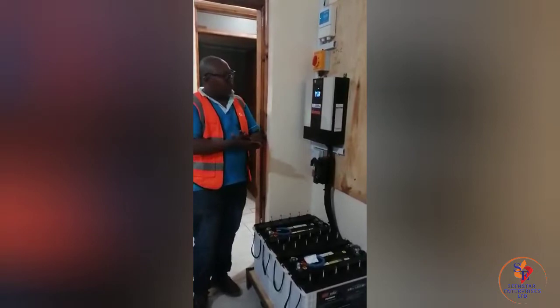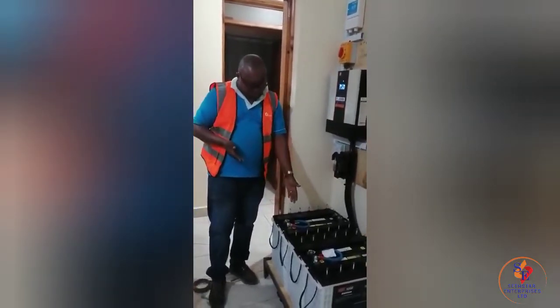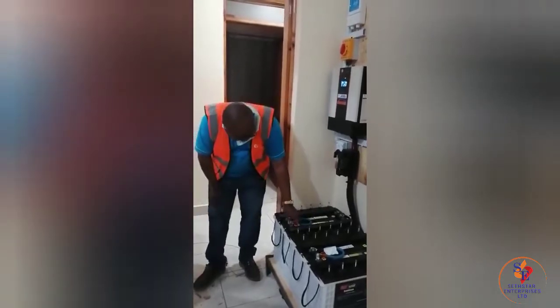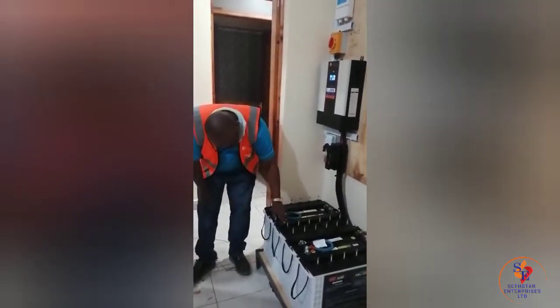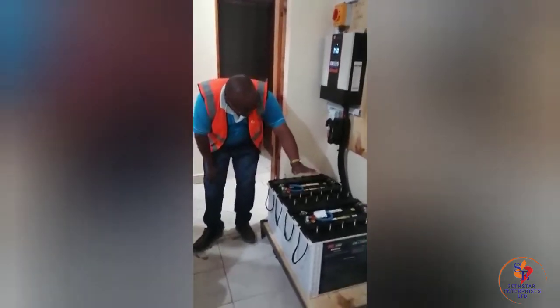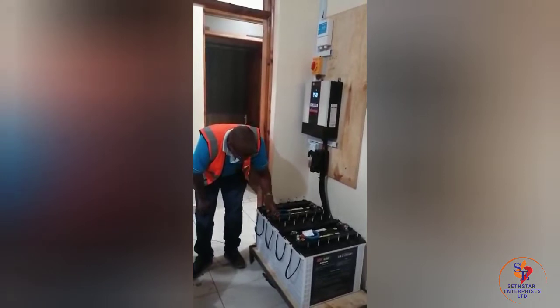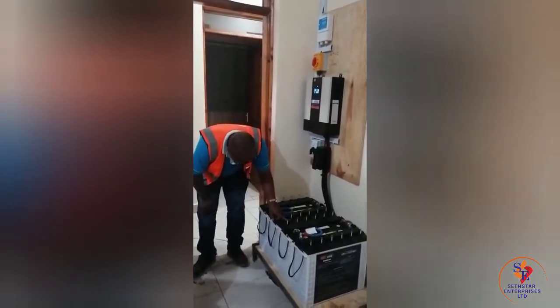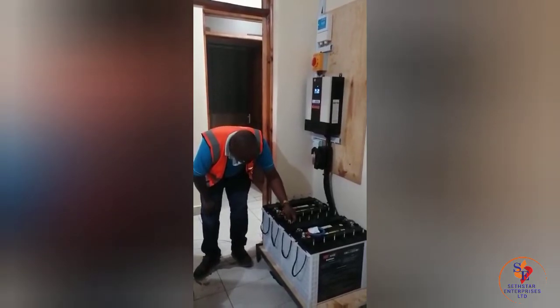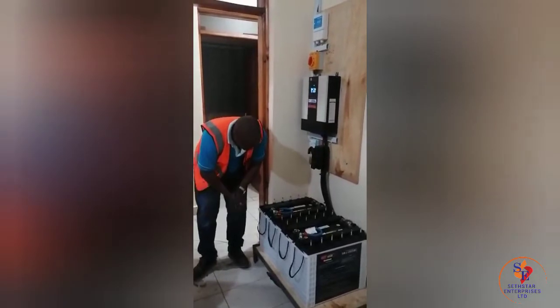So, for the general operations of the system, let's go to the batteries. These are floaters. Under here, you find that the floaters are on top — there is no float that has gone down. But after some time, maybe after six months or one year, you start noticing that the red mark goes down. So whenever you see it coming down, you need to get battery water to top up. Right now they are all safe, they are full.